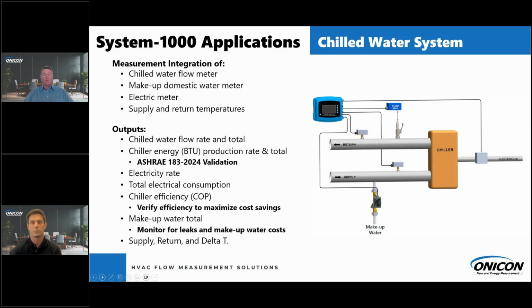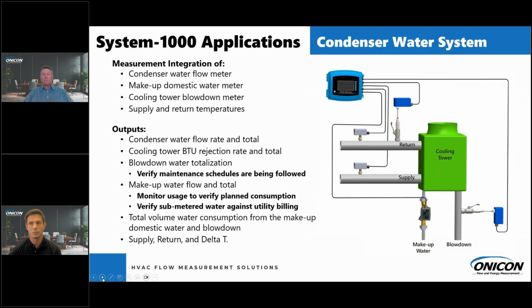We can also then bring in another meter for our makeup water total. With that, you can monitor for leaks, and you can also use it to monitor your makeup water costs to make sure that they're staying in line with what you budgeted. And of course, you're going to get your supply, return, and delta T out to your building management system.